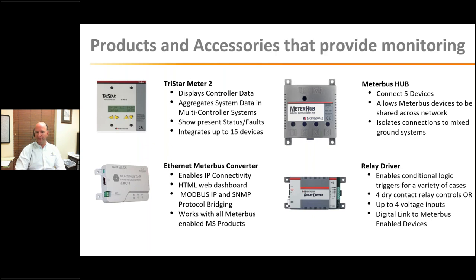They can actually drive 3/4 of an amp on the coil, meaning we can switch 60 or even 100 amp very large current handling relays that not only drive power, but also can signal alarms and faults. And there's four of those, which can also act as voltage inputs. So it's a very capable device, a very flexible one.